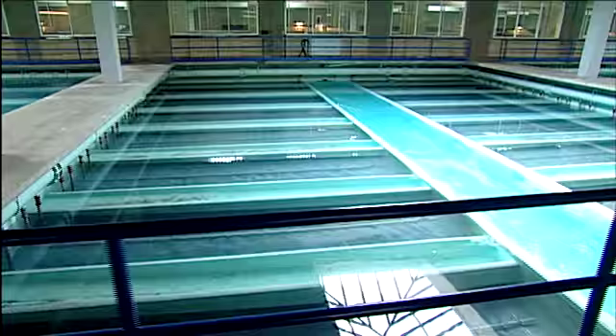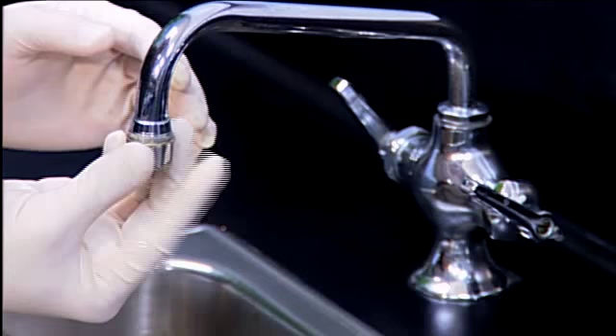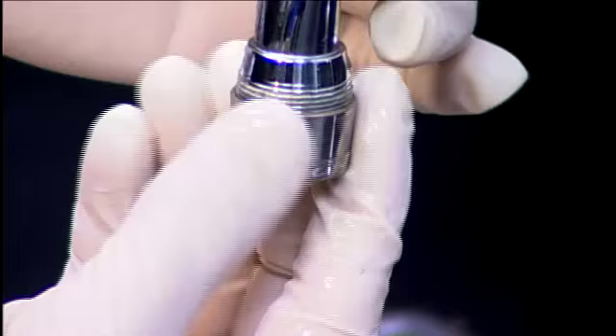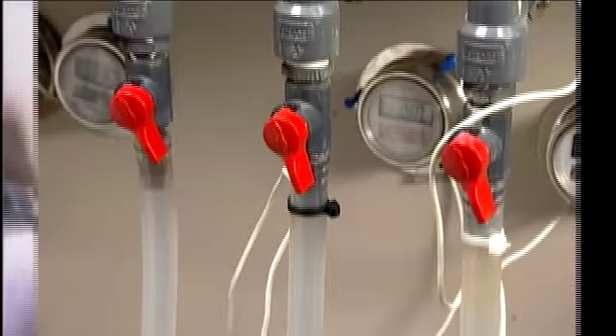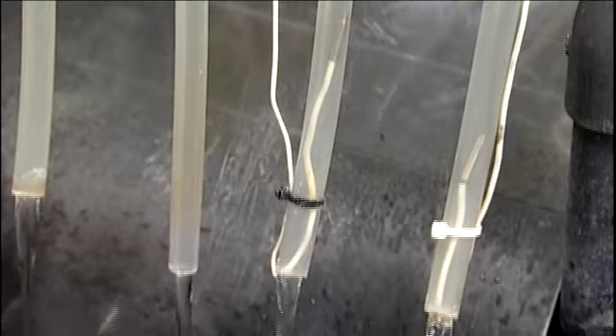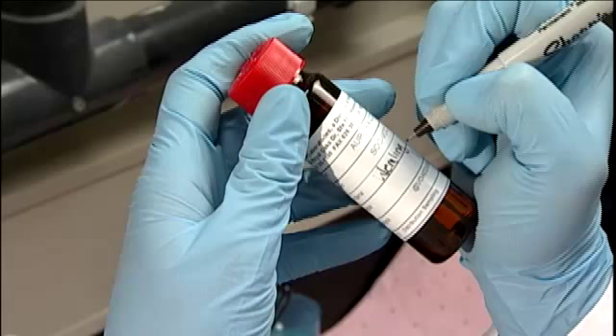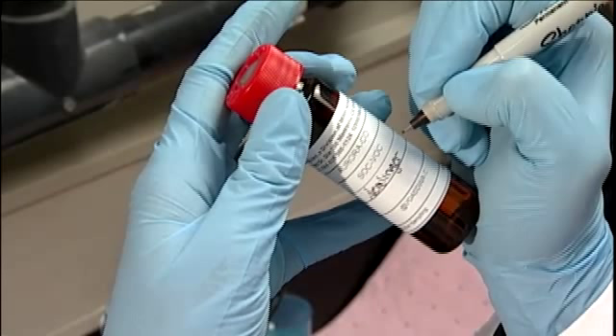VOC samples are taken at the point of entry — that is, the point at which finished drinking water enters the distribution system. Some plants have permanent sample taps for this purpose; if yours does not, select the sample location carefully. Generally for all sample tap use, except lead, remove any aerator before sample collection. Begin by adequately flushing the sample tap to ensure the sample is representative of the source. This may take from three to five minutes.